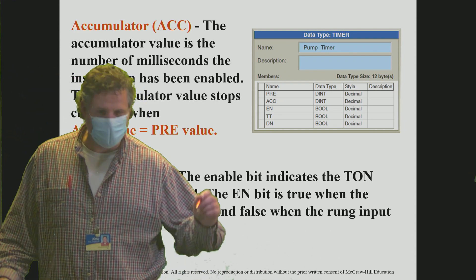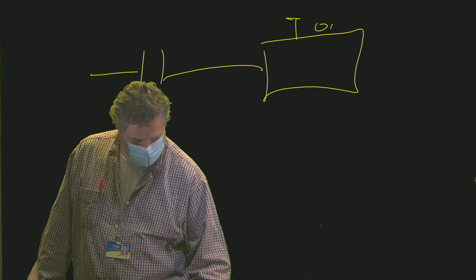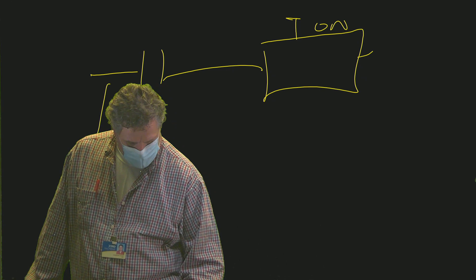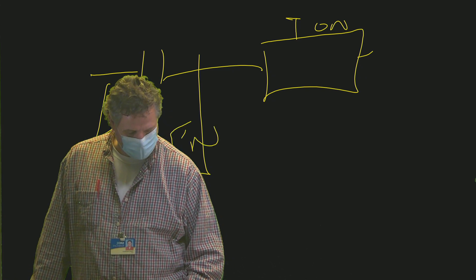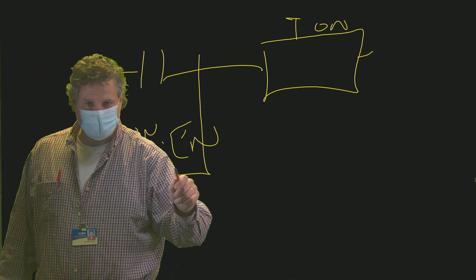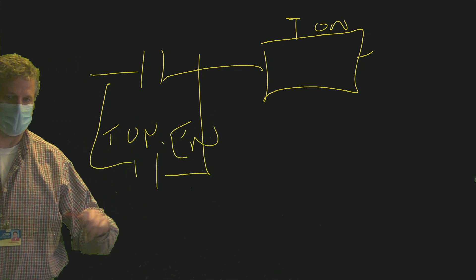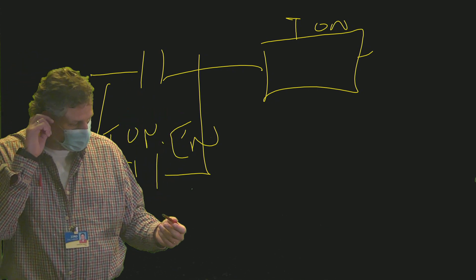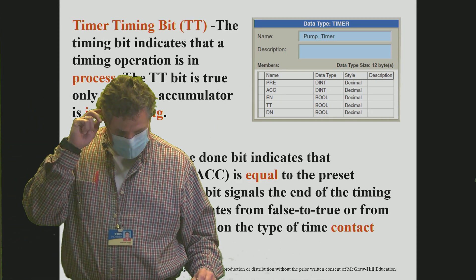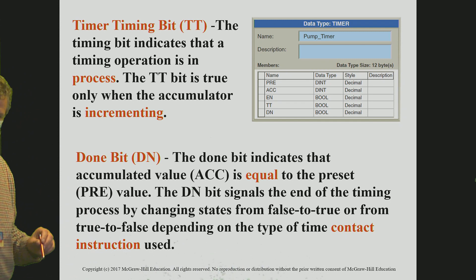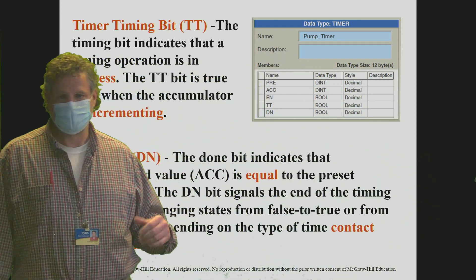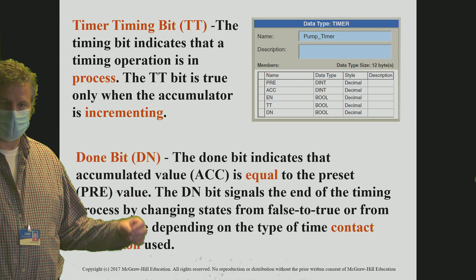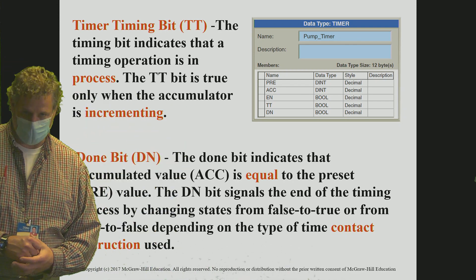The enable bit can be handy for doing a seal-in circuit. You can bring the EN around the input contact — using TON.EN — so as soon as you close that contact, it enables the timer, allowing it to stay on and continue timing. You do not have to hold the button to maintain timing. The timer timing bit (TT) comes on as long as that accumulator value is incrementing — when it's timing, the timer timing bit is on.